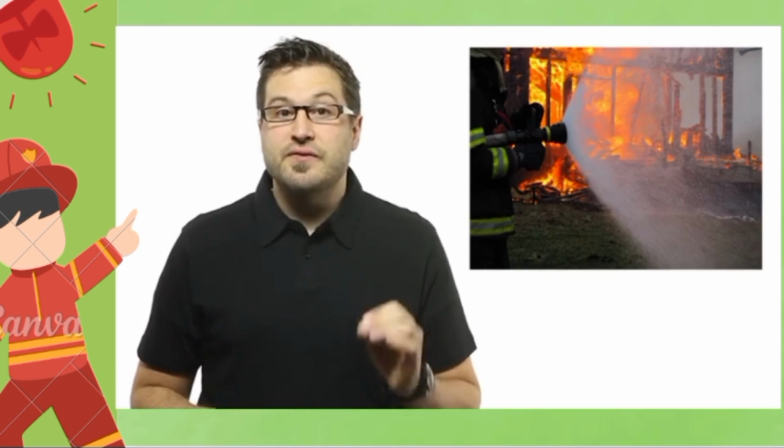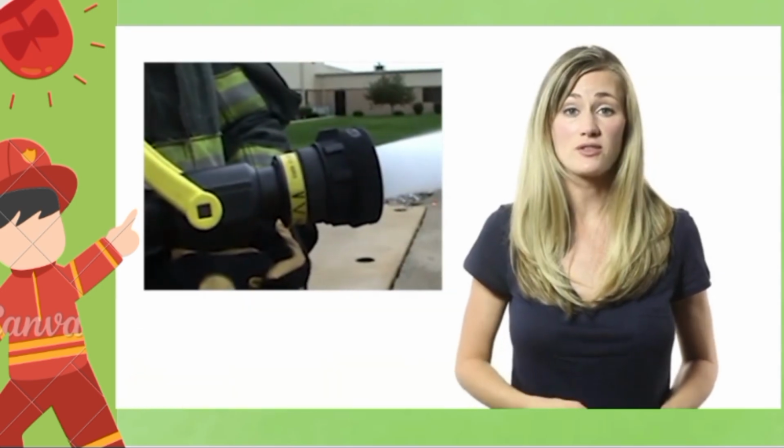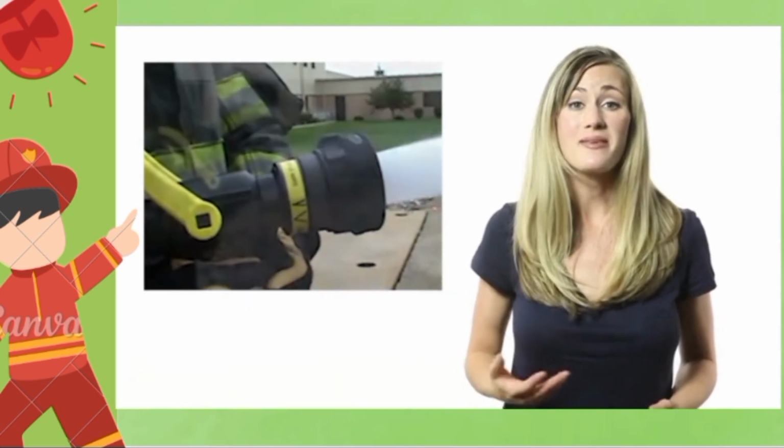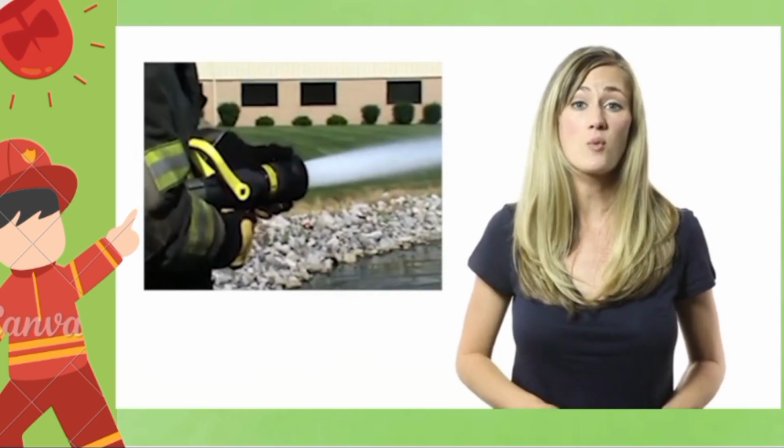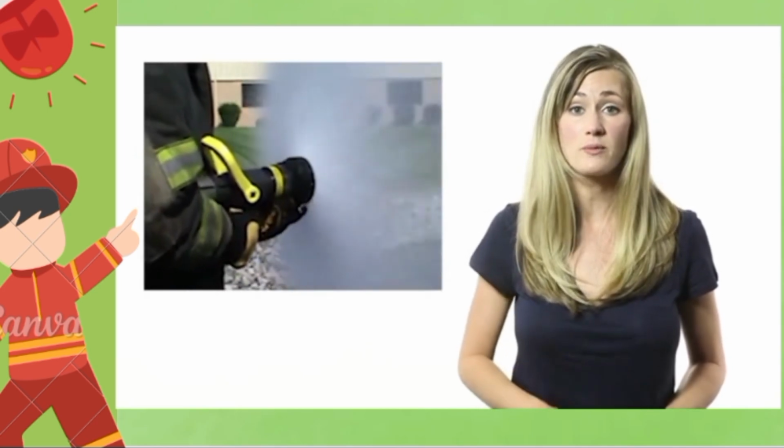This ensures that the controlling gap at the baffle remains constant, and a pressure drop will not cause a severe decrease in the amount of water flow. To allow a fire crew to use the nozzle for a variety of locations, the baffle is interchangeable, so the fire crews can match the nozzle to their desired water flow to get an optimum stream quality.